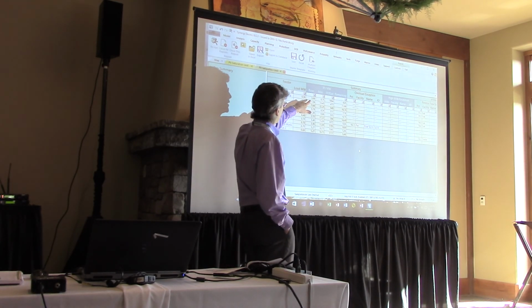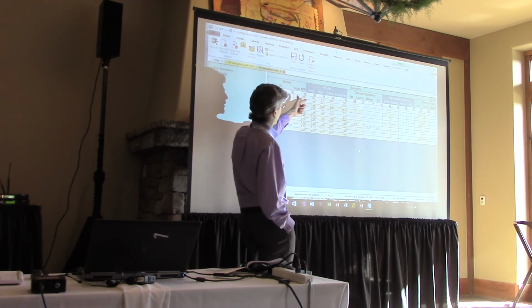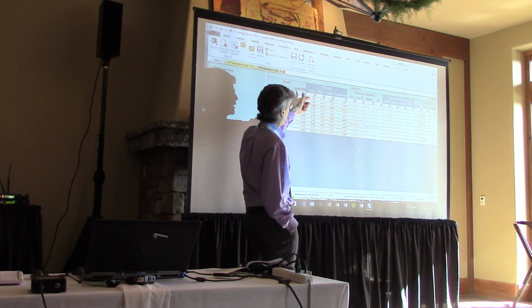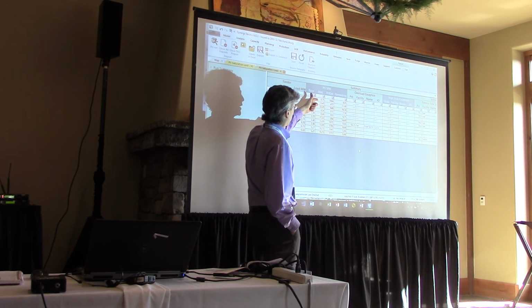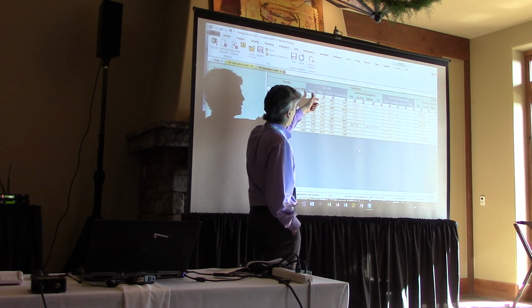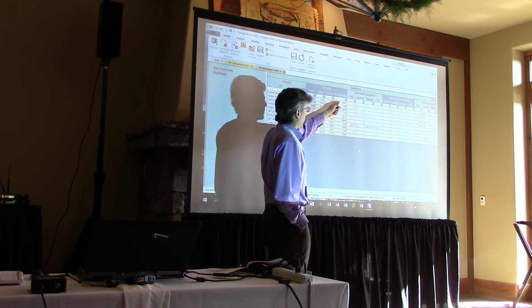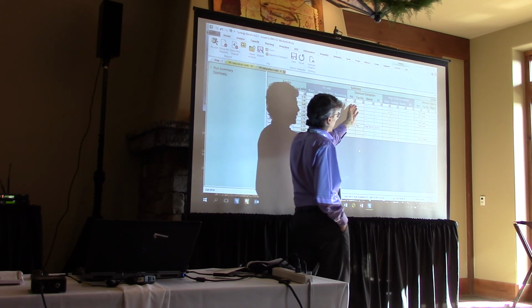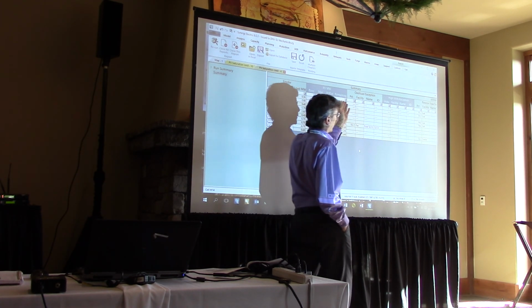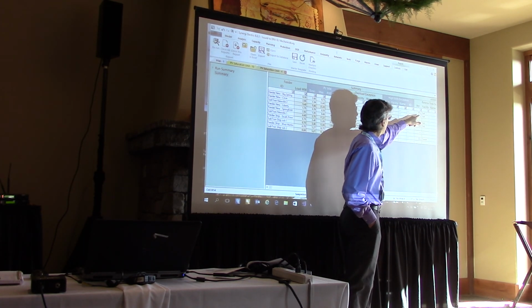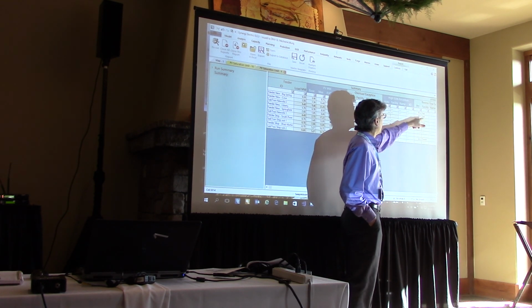And then we have how much. So this feeder, New Big Spring, has almost 4 megawatts PV on it, and it can get up to about 9. And so we've got about 5 remaining. So we look across here to say, okay, what is the limiting factor? It's, I'm sorry, the reverse flow.